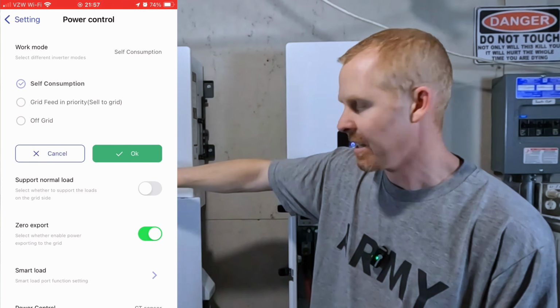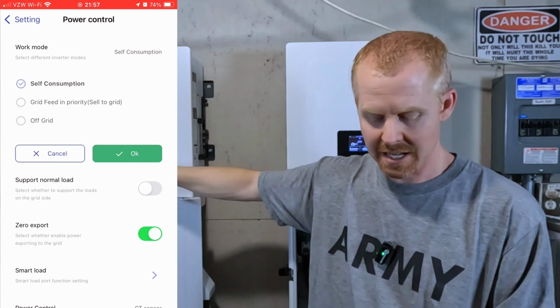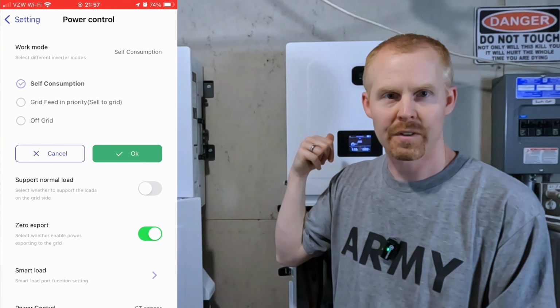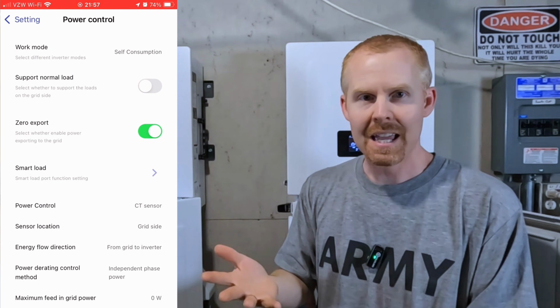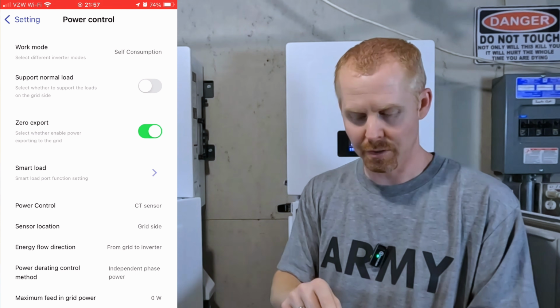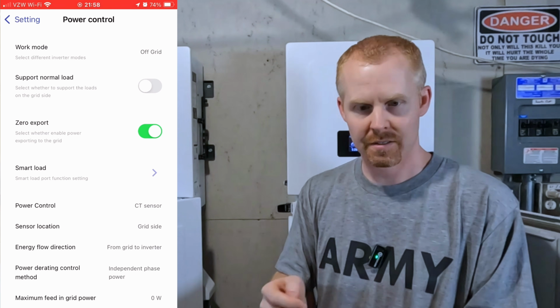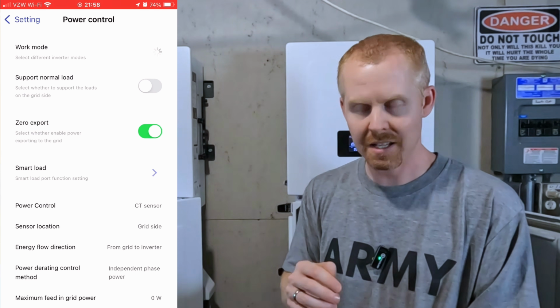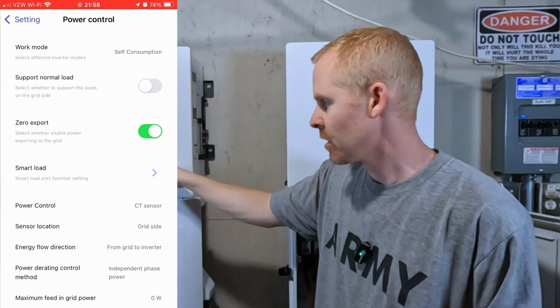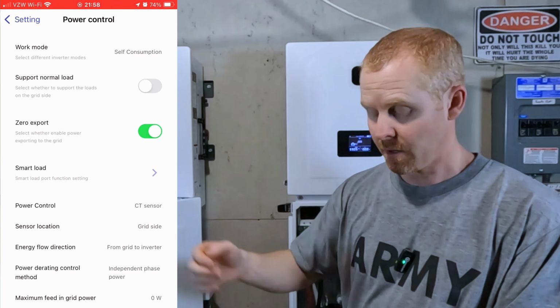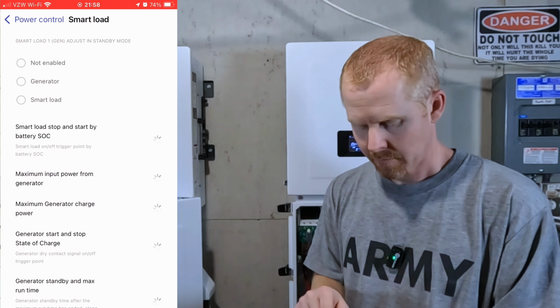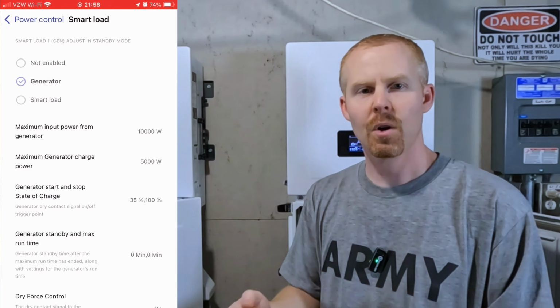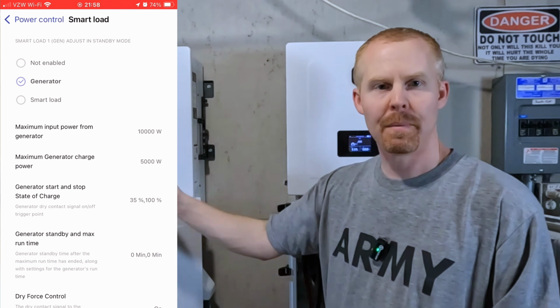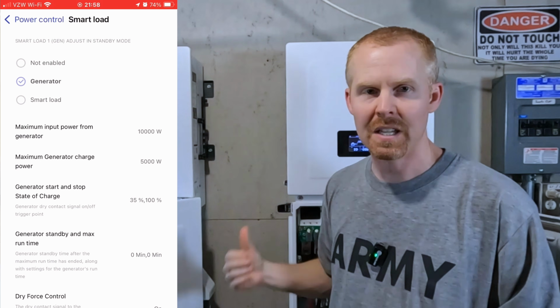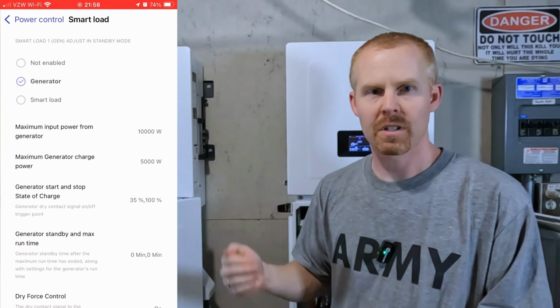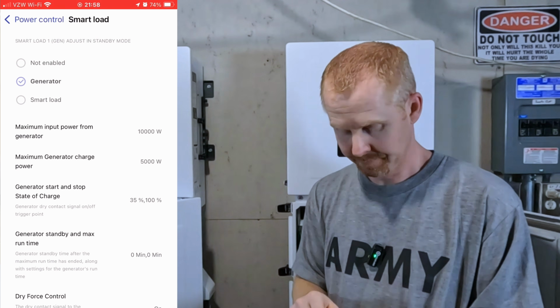So right now my slave inverter actually thinks that it's in an off-grid state, but this inverter is self-consumption. Now if I just hit OK, it doesn't actually push the change to the inverter. So I need to change it to something else and then switch to self-consumption again, and that will push the change to this inverter. So we want to do that with our working mode. If you are using the generator or AC coupling, you have to set that up on both inverters. So you would set up a feed for the generator in both, and then you would configure the same thing for your AC coupling as well.